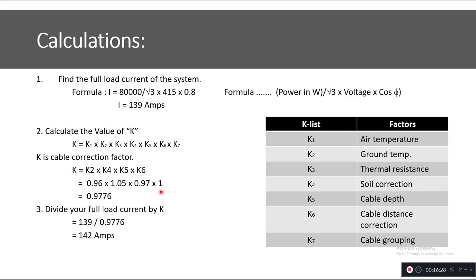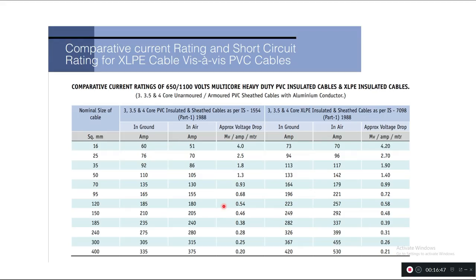The next step is to divide the full load current by K: 139 ÷ 0.9776 = 142 A. This means the cable's minimum current carrying capacity must be at least 142 A. Referring to the cable datasheet for XLPE heavy duty underground cable, the 70 mm² cable carries 164 A and the 95 mm² cable carries 196 A.